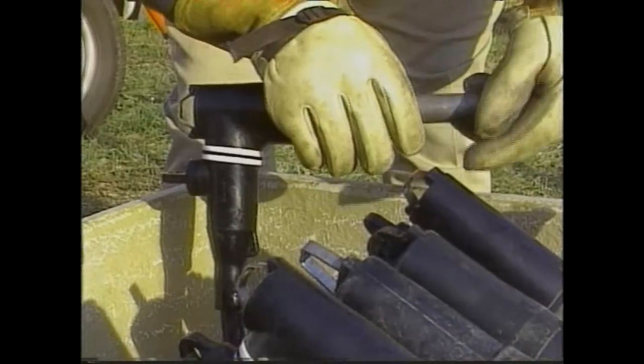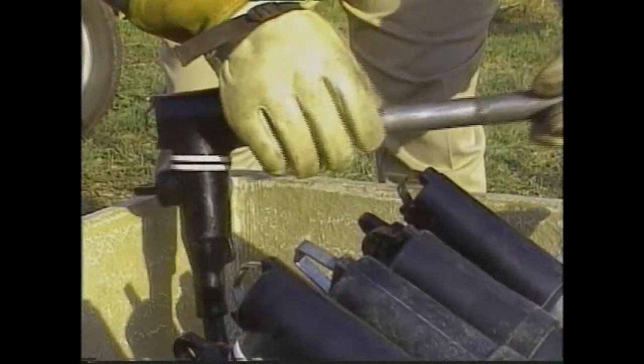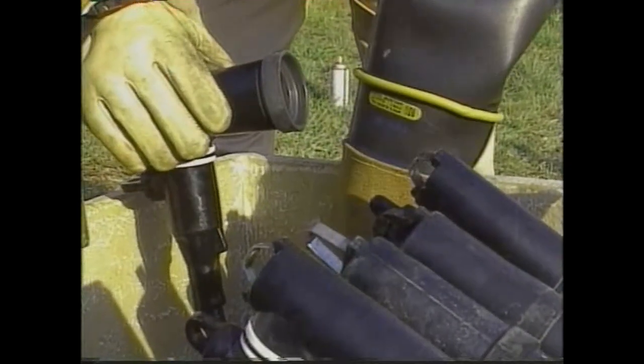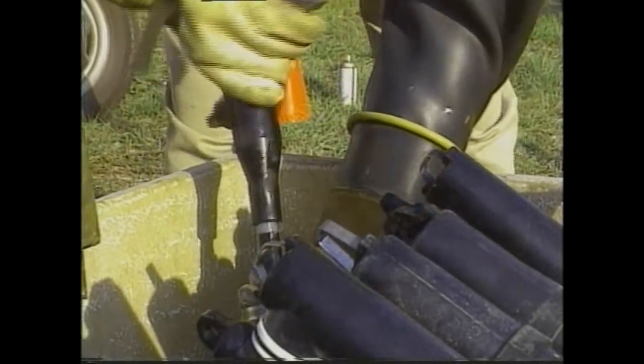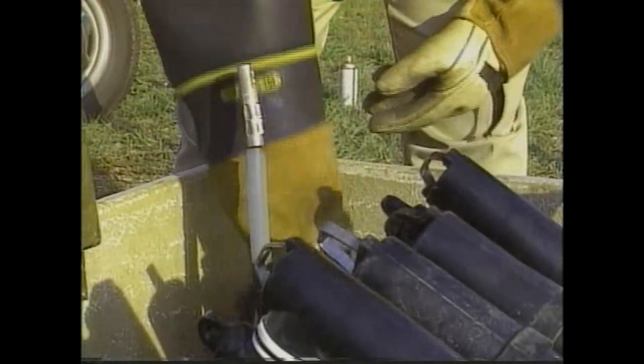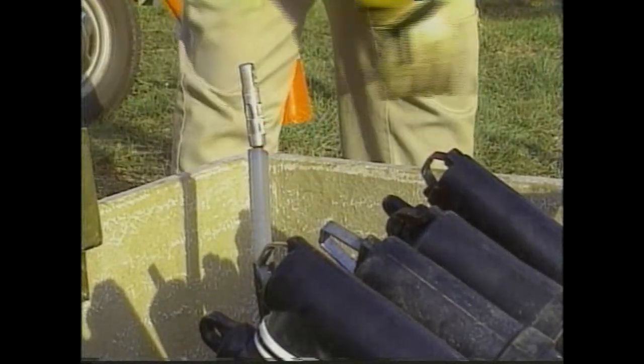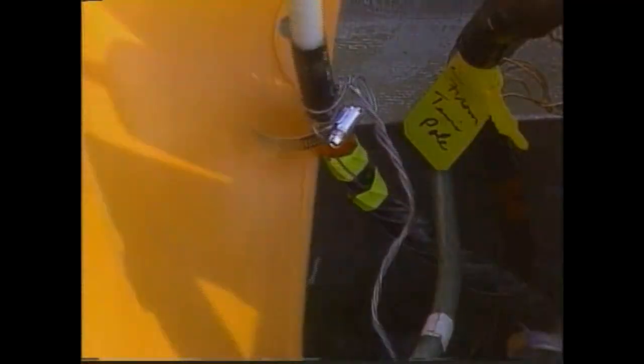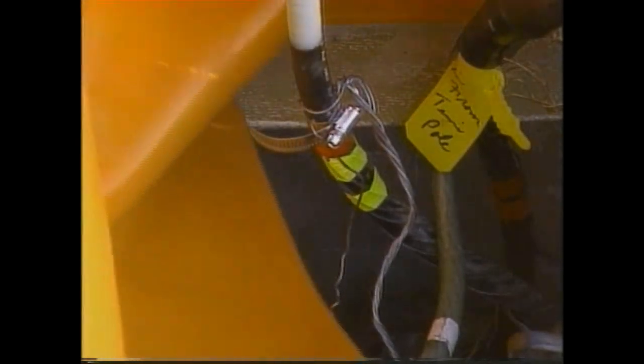To remove the elbow, we must first remove the center bushing in the elbow. Now that the bushing has been removed, we can pull the elbow off. With the elbow removed and the conductor exposed, we should install a high-voltage rubber blanket that can be used to seal off the thumper connection to the cable.